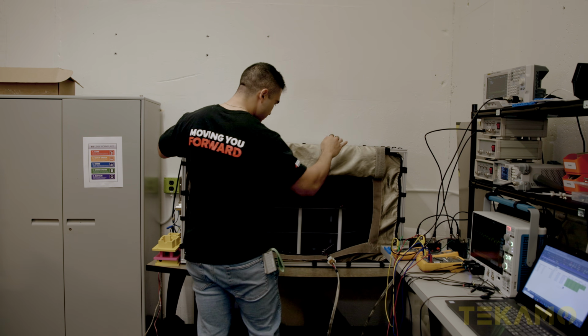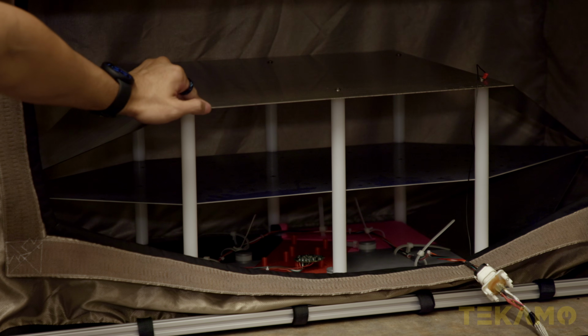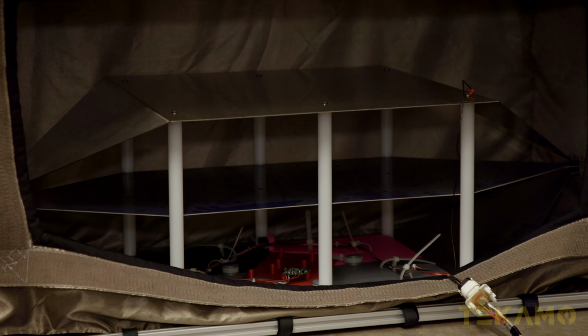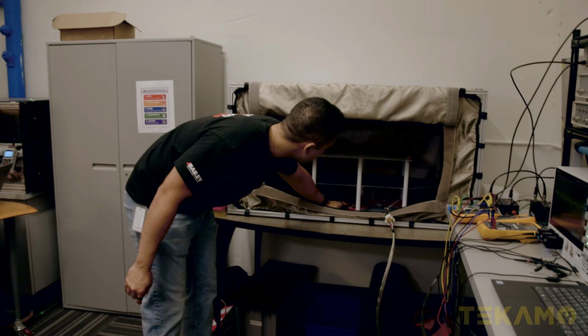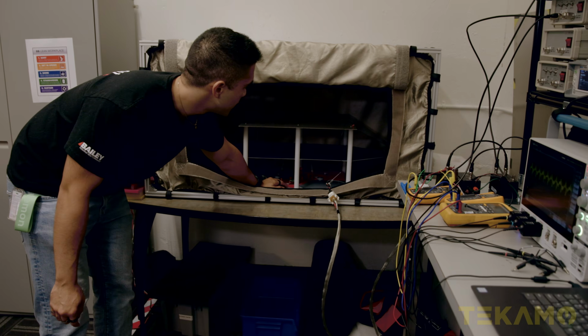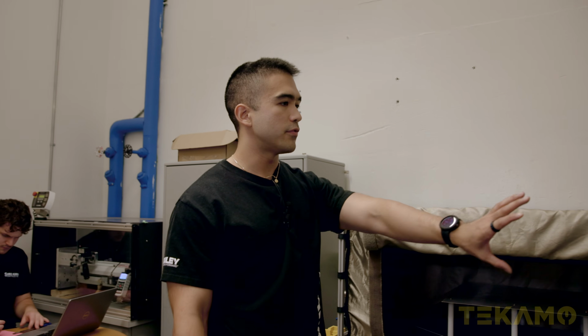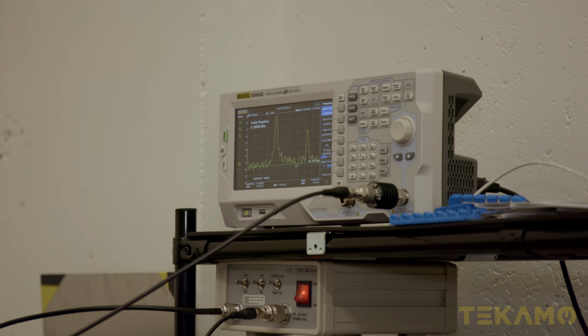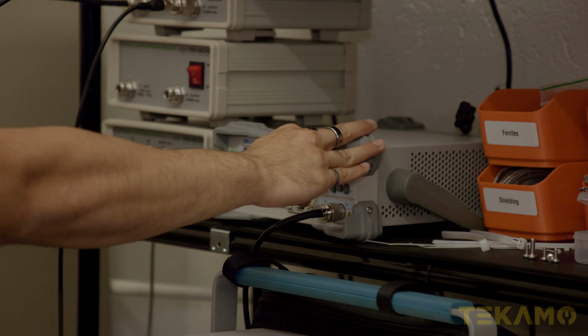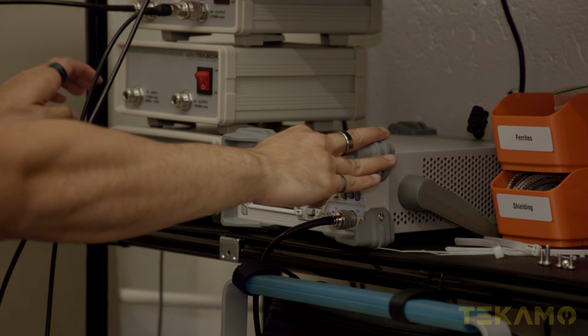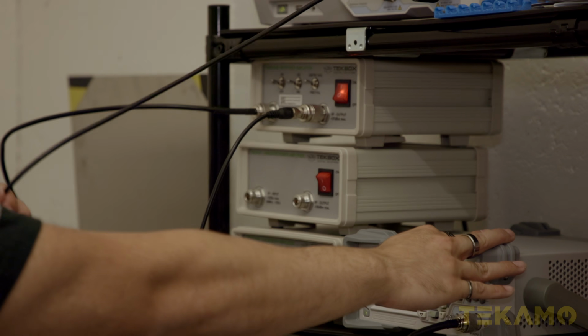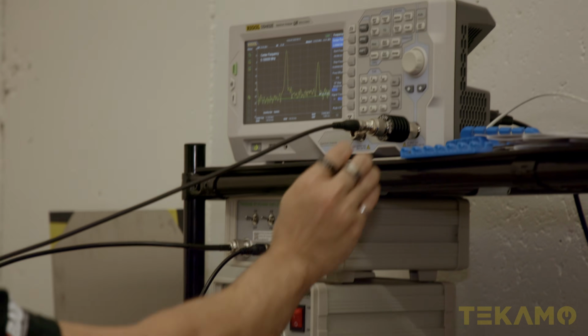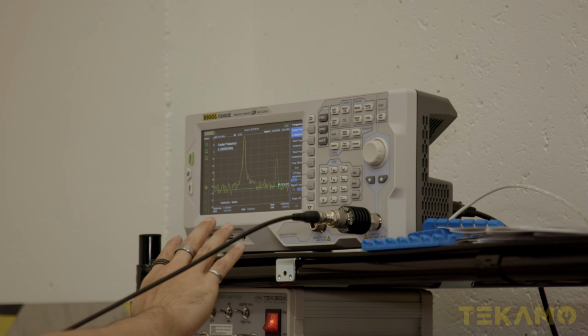So what we have here is called a TEM cell, short for transverse electromagnetic cell. This allows us to put our device into the cell and subject it to power from our devices here. We can apply specific radio frequencies to our device at specific power levels and see how it performs. Essentially, this lets us see if our device will fail or pass out in the field.